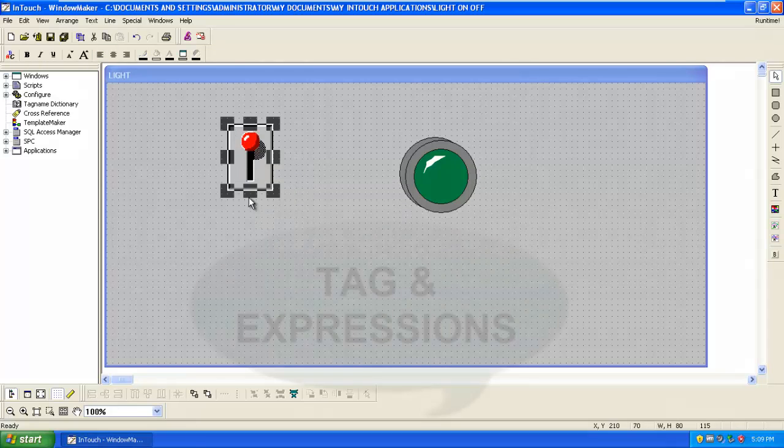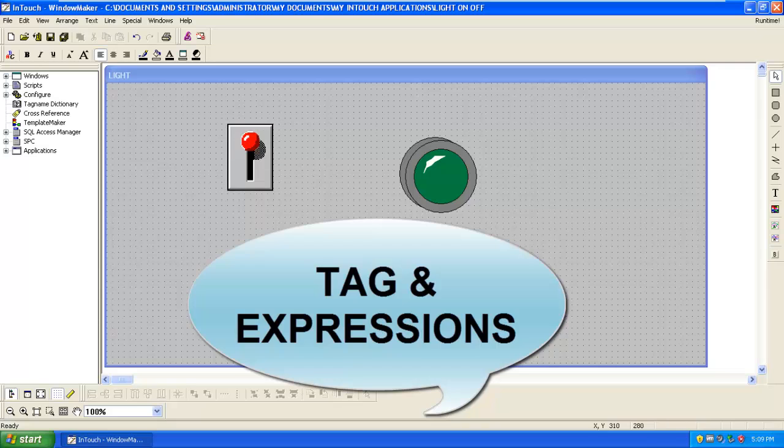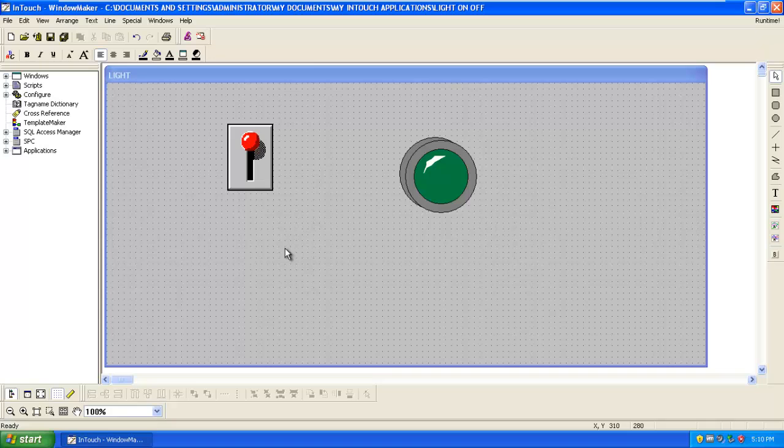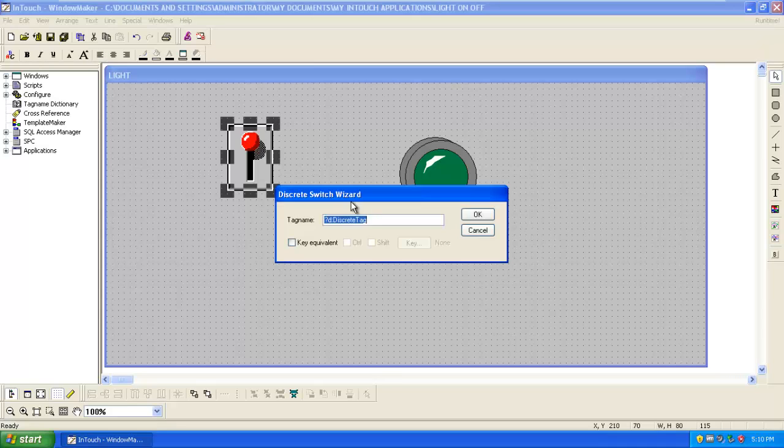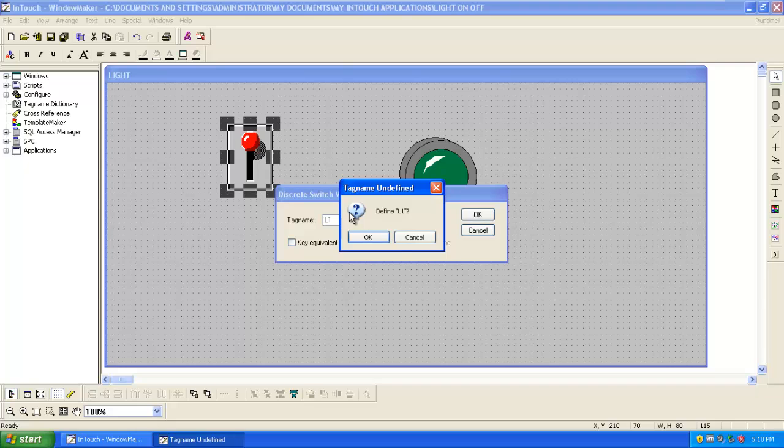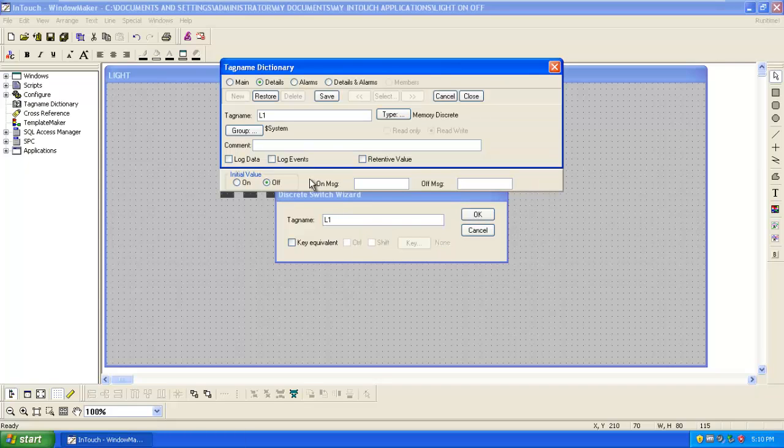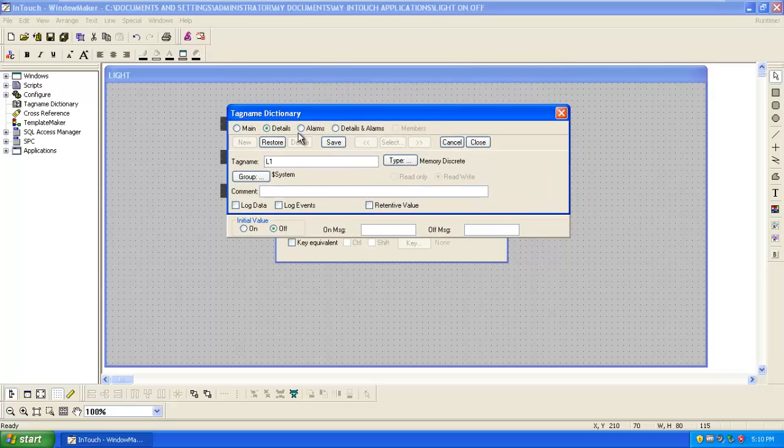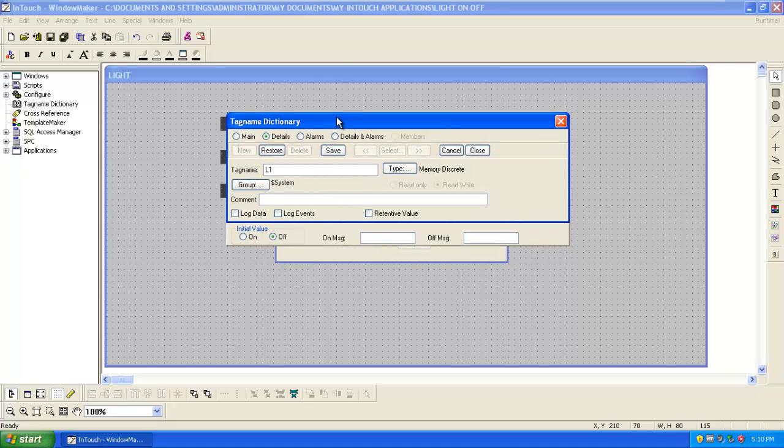Now the most important part from the SCADA. You have to tag the items for its identification. So double click on the icon or switch. Then it will ask for the tag name. Give the tag name as L1, that is light1. Click on OK. Now you can give the alarms for the tag. So click save and close.